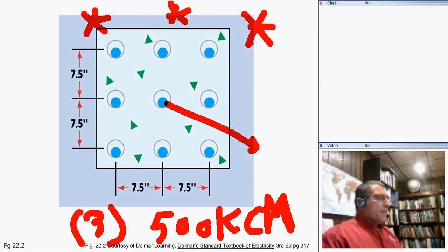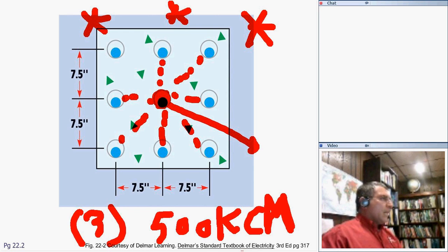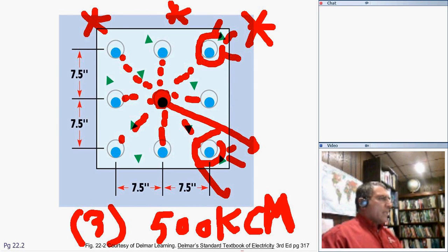How many of you guys have worked with ducts like this? It will be 1, 2, 3 times 3, 9 circuits, 500 kcm each, parallel circuits and so forth. Now this conductor right in here is your weakest link, because this one is trapped, right? Can you guys see the trap? The heat is going to be coming from all these ducts, and this one is trapped. All the ducts are contributing heat, heating the block. This one here can dissipate heat further, right? Can you see the perimeter one? It dissipates heat faster. Anyway, the worst scenario for this duct bank is going to be the one right in here. That's the one that's going to decide how much current the whole configuration is going to carry.